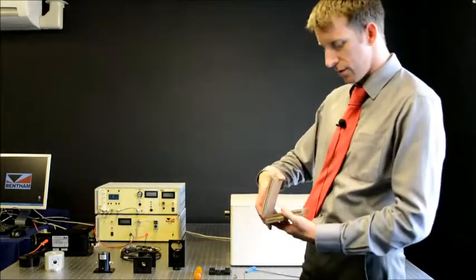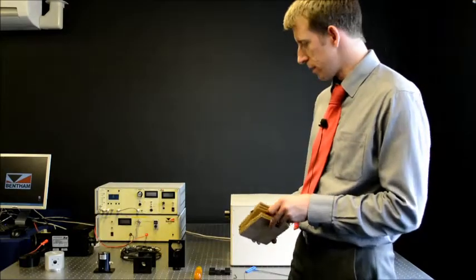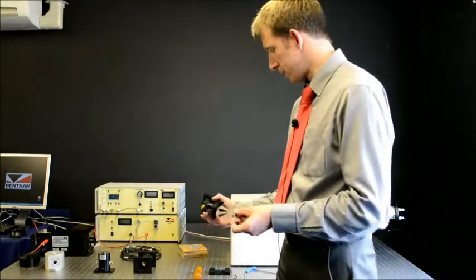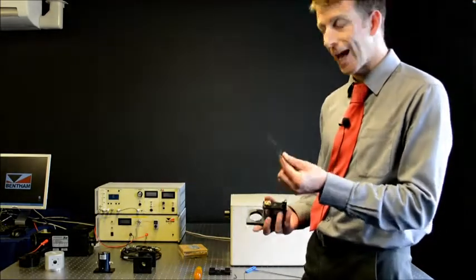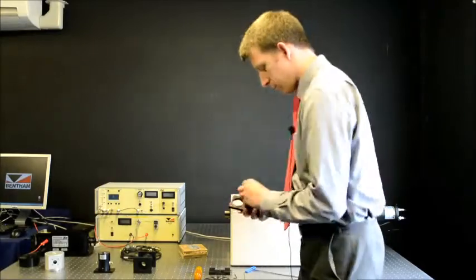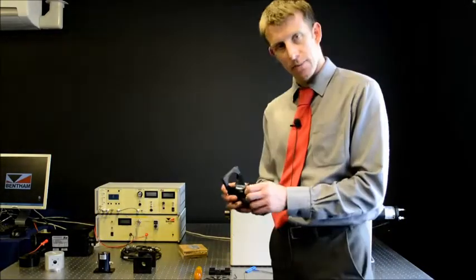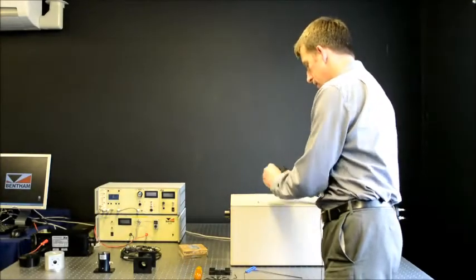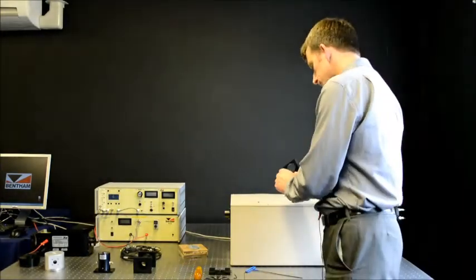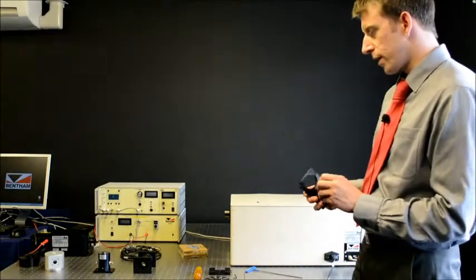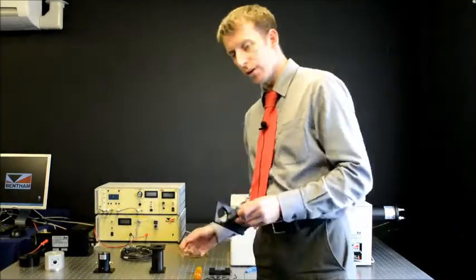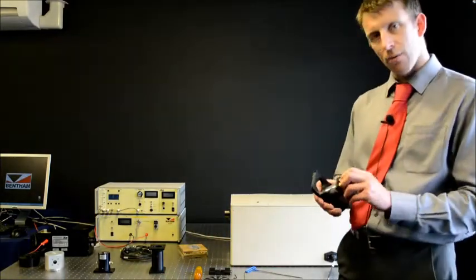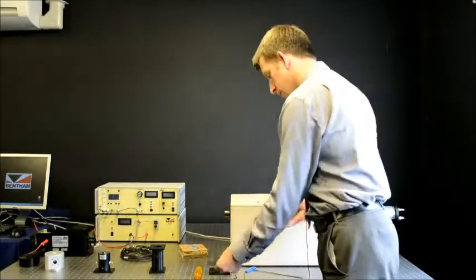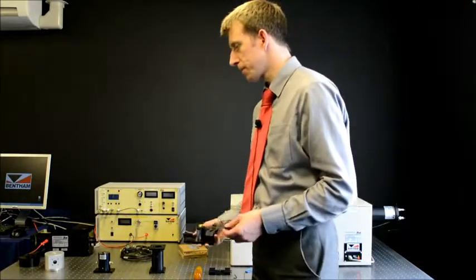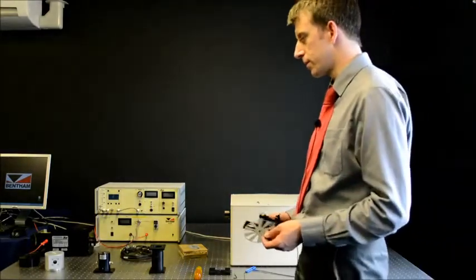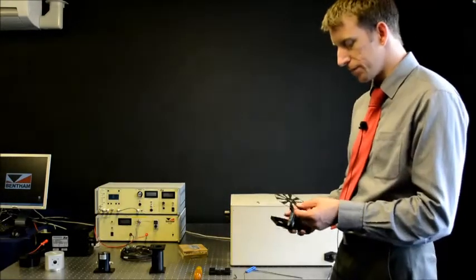The optical chopper provided is the 218 optical chopper, and a set of blades has been provided. And here we will use a 10-slot blade. For the first time, we need to set up the infrared input optic. It consists of a calcium fluoride based relay optic. We have a mount for the optical chopper which will sit on the relay optic, and we will also discuss the use of the sphere, the D8 sphere, as an input optic.